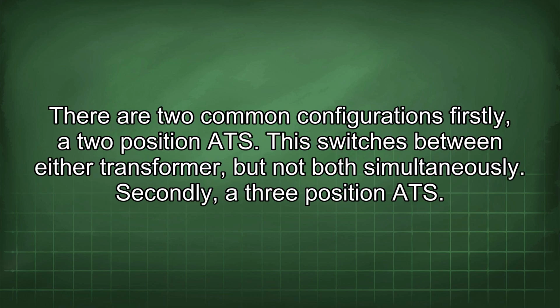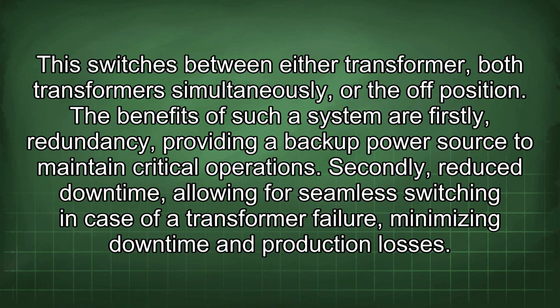There are two common configurations. Firstly, a 2-position ATS. This switches between either transformer, but not both simultaneously. Secondly, a 3-position ATS. This switches between either transformer, both transformers simultaneously, or the off position.